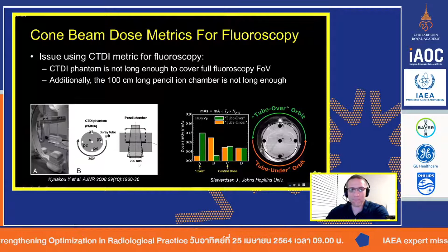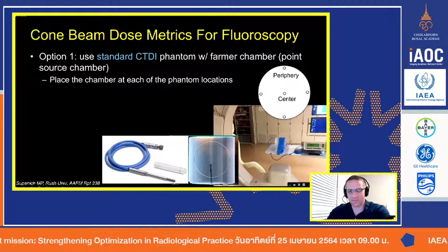So here we go. You can use the CTDI phantom as it is. It's a simple 16 centimeter phantom, so it's not super wide. You can't see the whole detector here, but you get the idea: here's the X-ray tube, which itself is bigger than that. You place the ion chamber in it. There's a small difference though. Instead of using the 100 millimeter probe, we're going to use a small probe called a Farmer chamber. So we're actually doing a point dose calculation, and we're still going to place the probe in each of the locations.